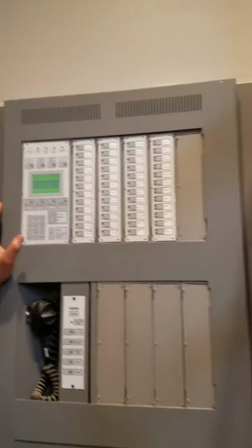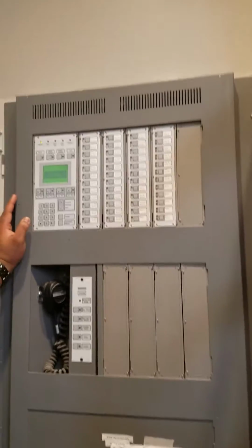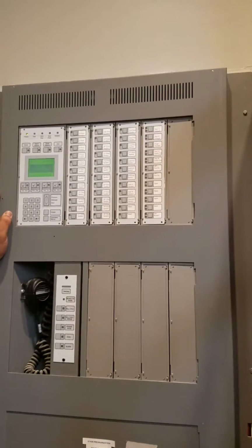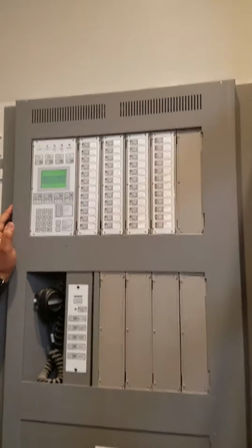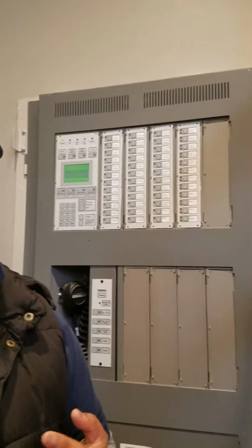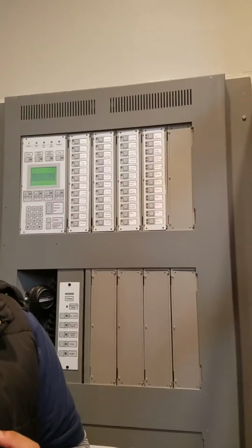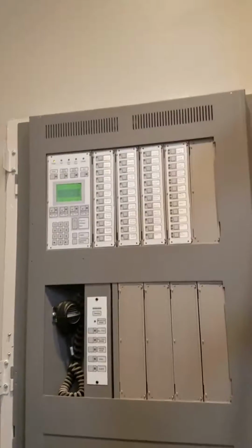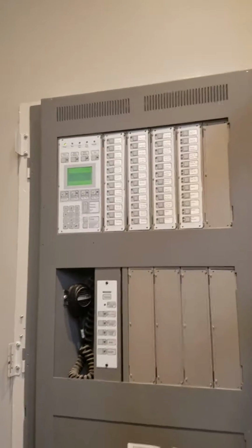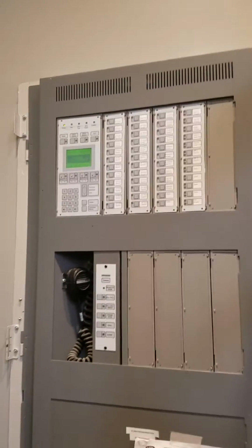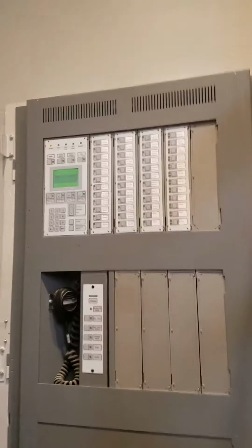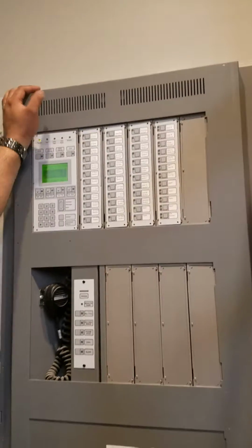So a smoke fire alarm would not recall the elevators? No. Well, in front of the elevators, yes. It would have to be a lobby smoke, or top of the elevator shaft. Inside each apartment it won't. Those will shut down your fans. The regular smokes will shut down your fans, but anything associated with the elevator would be your lobby smokes, your water flow would definitely do it.